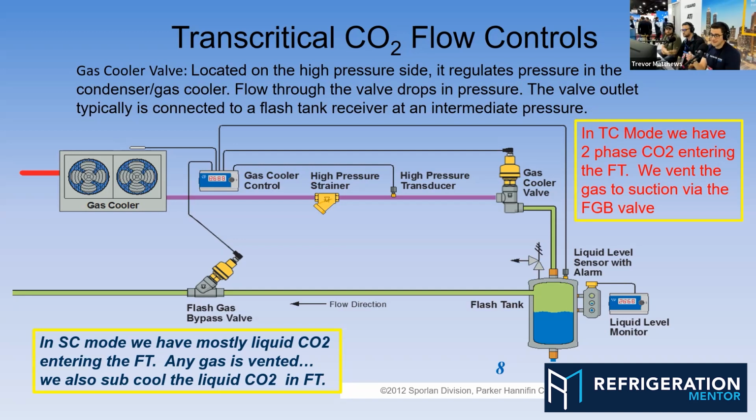So are all those inputs going back to this controller, the MT 742? Are all those inputs going back to that controller, and it's thinking about them and then adjusting the valve at that point? Right. What I'm going to show you that Chad set up for me, they're all going back to the combined train, which is the gas cooler node along with the 2-valve controller merged into one train. And then I will show you when I log into another site. I can't show you everything because there's some proprietary MPCs, but you'll see that there's a gas cooler node and there's, I'll call it, a freestanding 2-valve controller, and the inputs are going to various places, and then we're sharing those inputs through bindings. And you're basically doing like 3 functions here all at once.